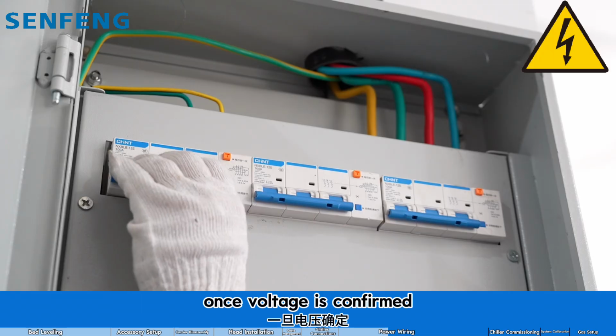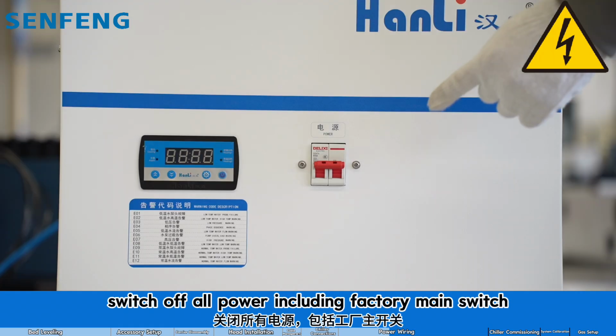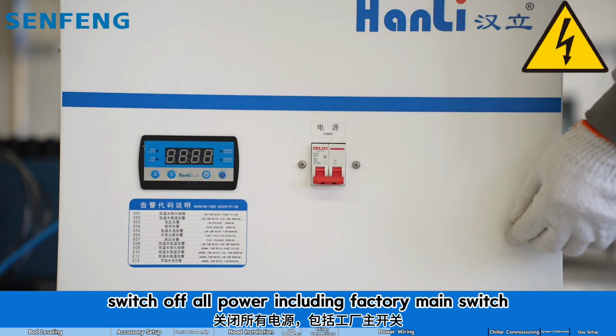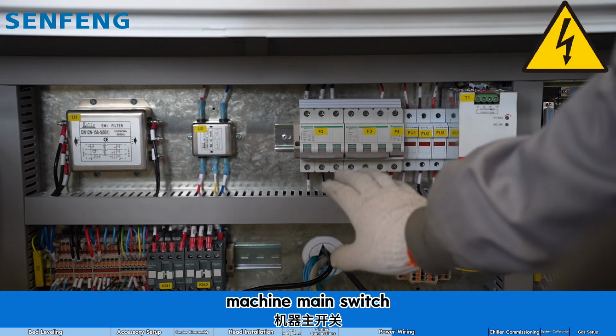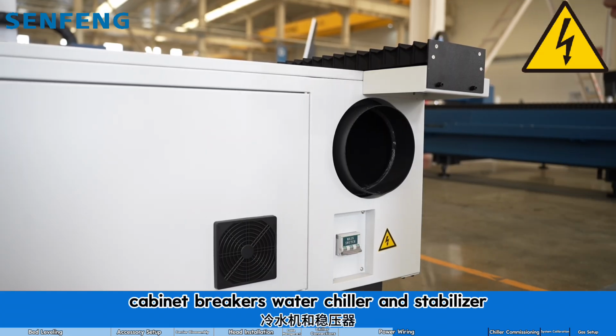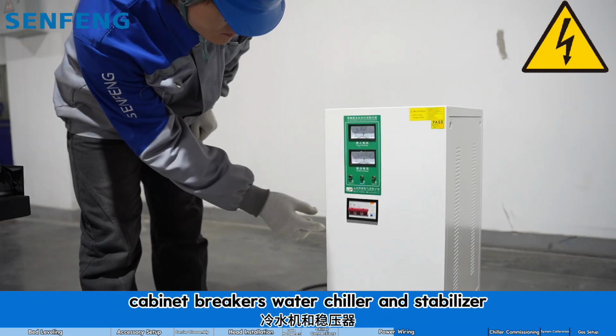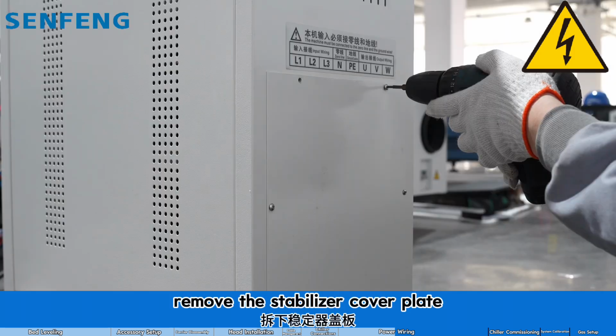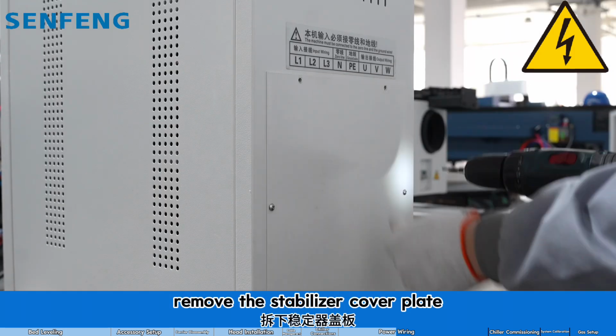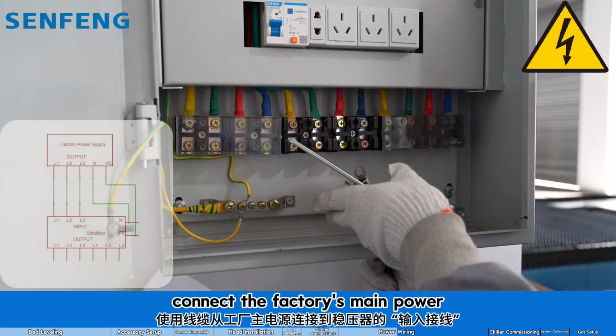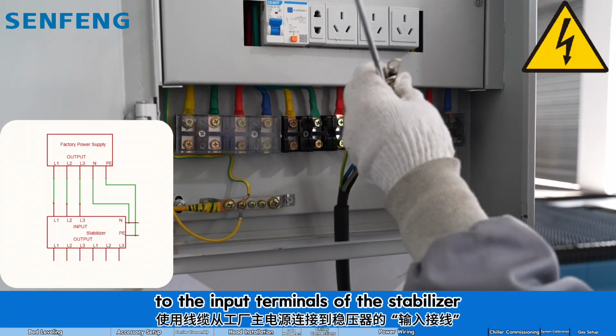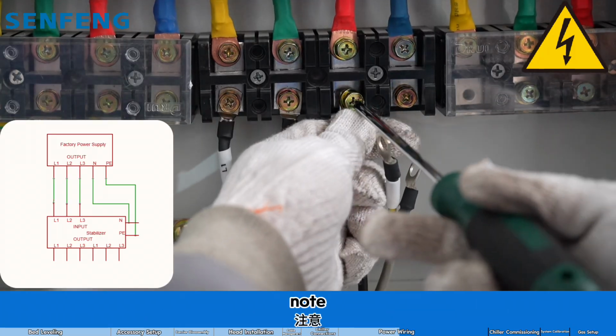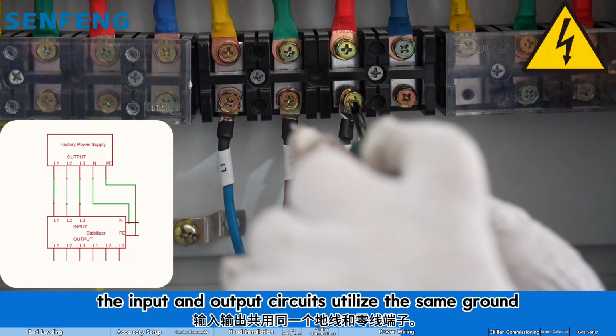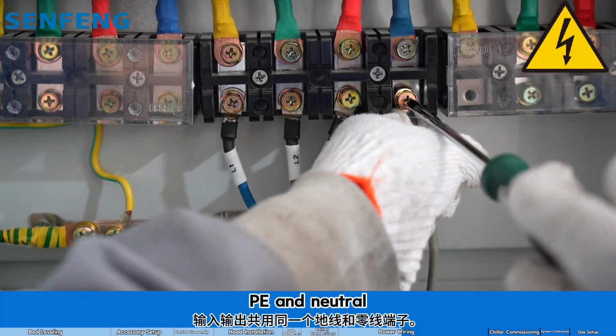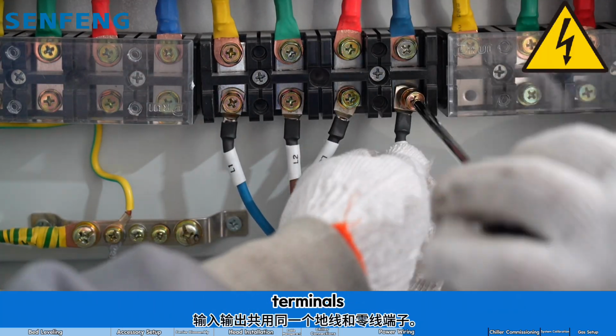Once voltage is confirmed, switch off all power, including the factory main switch, machine main switch, cabinet breakers, water chiller, and stabilizer. Remove the stabilizer cover plate. Connect the factory's main power to the input terminals of the stabilizer. Note: the input and output circuits utilize the same ground, PE, and neutral terminals.